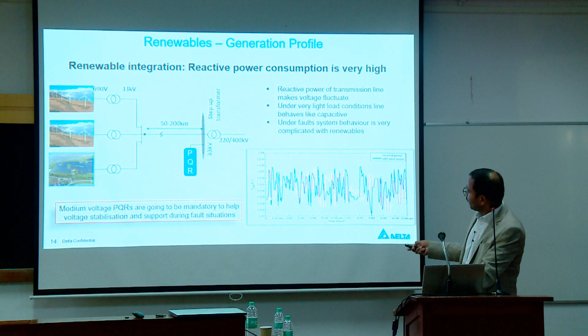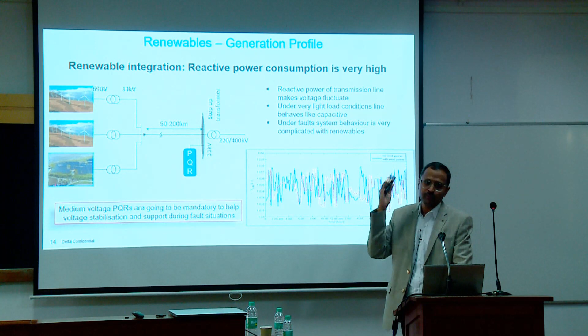To support the same thing, I have taken some data from the German grid. If you don't have wind farms connected to a certain grid, you have a voltage profile where the voltage is expected to vary, but it varies with a low frequency. But the moment you have wind turbines connected, you have higher frequencies. This frequency causes problems because this AC line always has a resonance, and it perturbs the resonance. At some location the voltage shoots up, and then the circuit breakers trip. If a 400 kV line crosses 480 and you don't protect it, the circuit breaker is gone. To fix that circuit breaker, you take at least 6 hours.